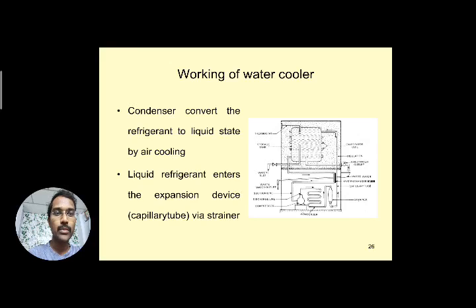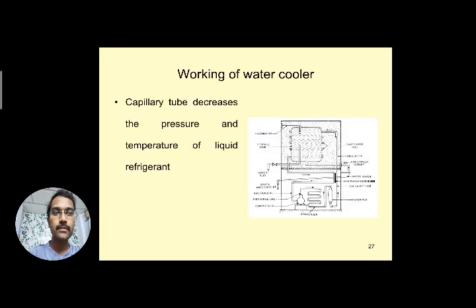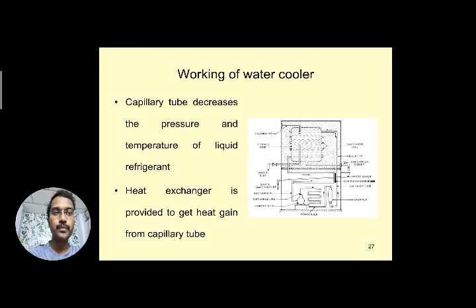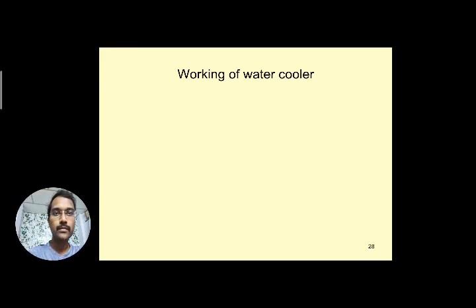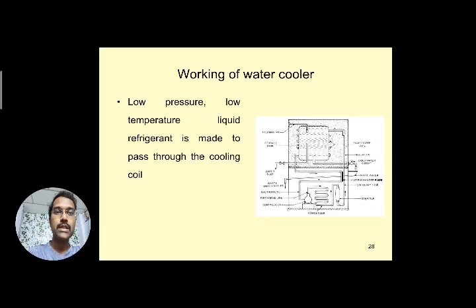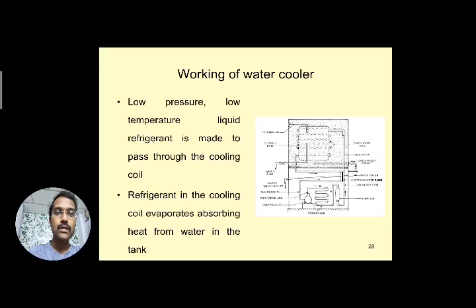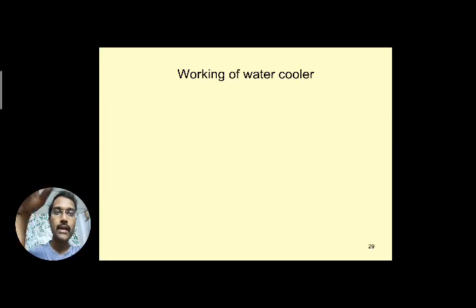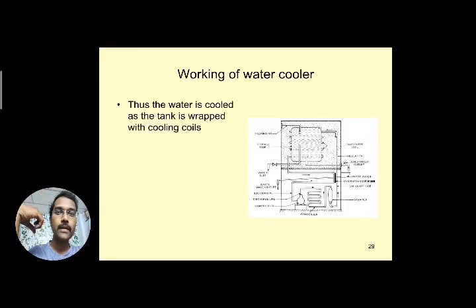In the condenser, a phase change occurs from vapor to high-pressure liquid refrigerant, cooled by air — forced type using a fan. The liquid refrigerant enters the strainer or dryer to remove moisture content, then the capillary tube decreases the pressure and temperature simultaneously. A heat exchanger is provided where the capillary tube meets the suction line, exchanging heat between the high-temperature liquid line and the cool suction line. The low-pressure, low-temperature liquid refrigerant then passes through the cooling coil.